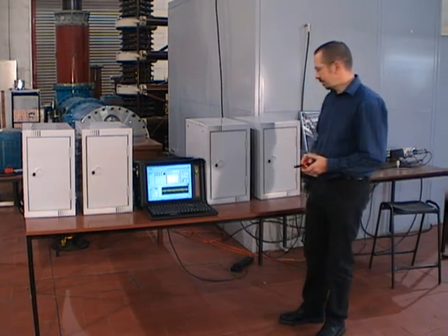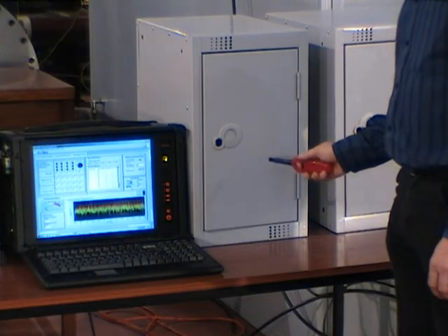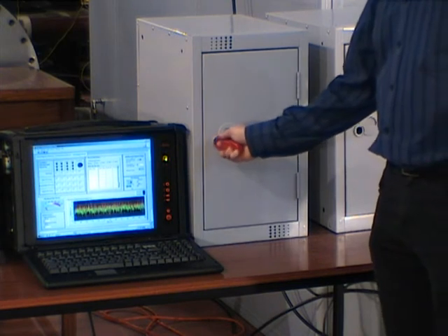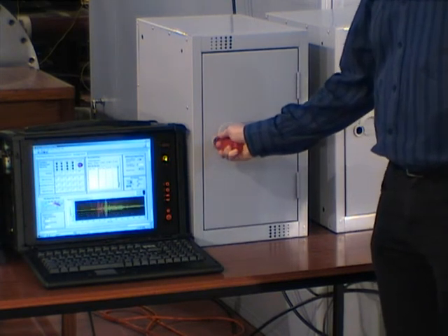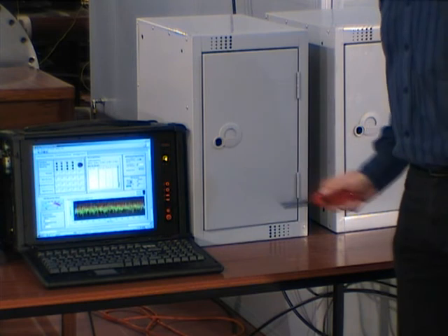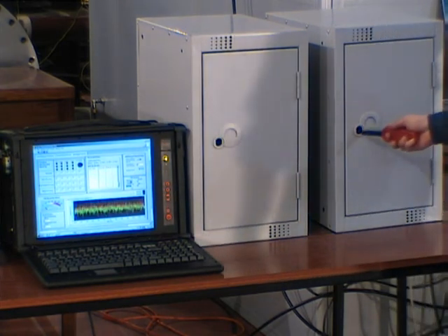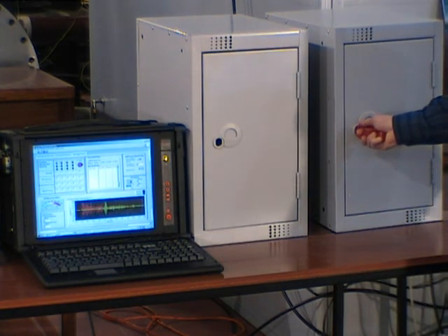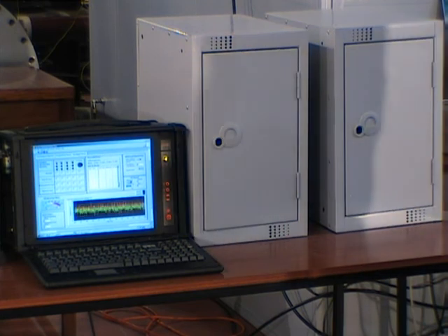If we insert the sparker into unit number 2 and fire it, the system detects partial discharge activity and indicates unit 2. Moving to unit 1, it should also detect that.